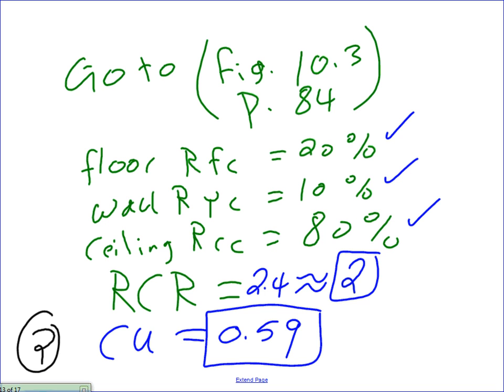The most important thing is that Fig here. Otherwise, you're not going to be able to use it. On the final, I'll get you a brand new one from Lithonia, but not this time. They're all the same. They go by the floor reflection, ceiling, and walls. Floor is usually neglected. Ceiling and walls are the most important things. Dark ceilings have a smaller reflection. Light color ceilings and floors have a higher reflection.